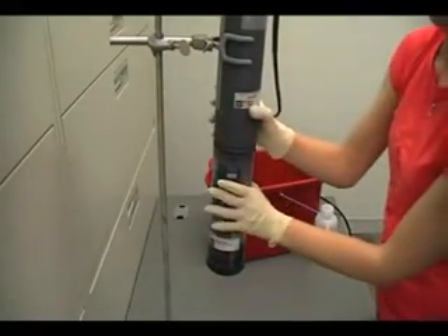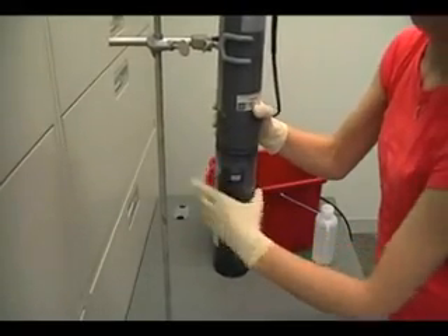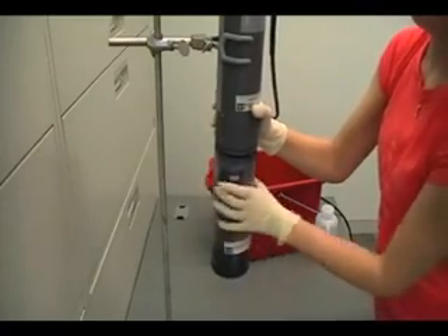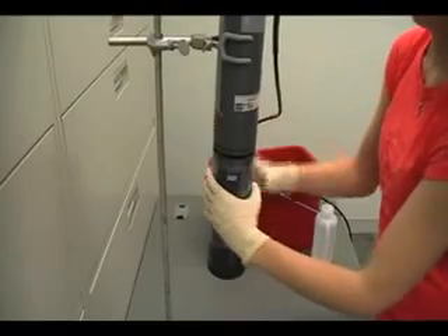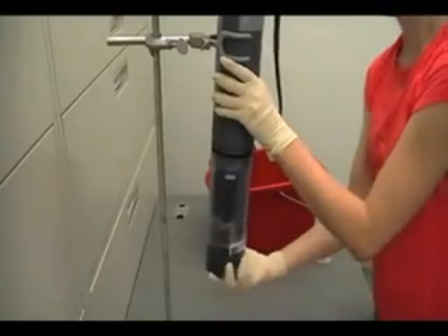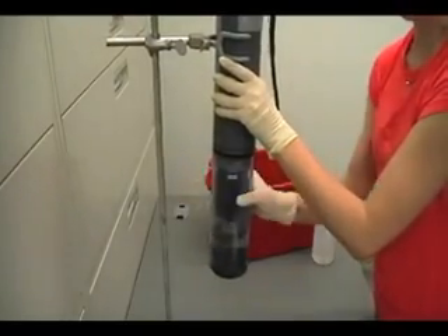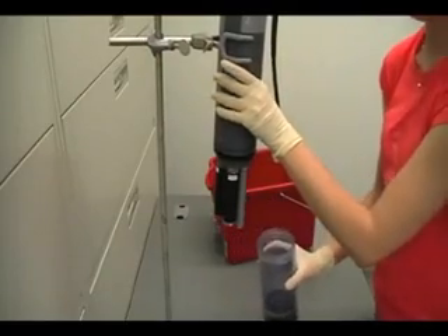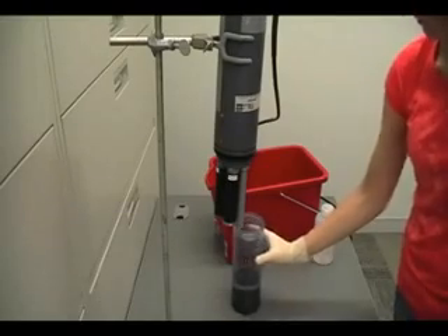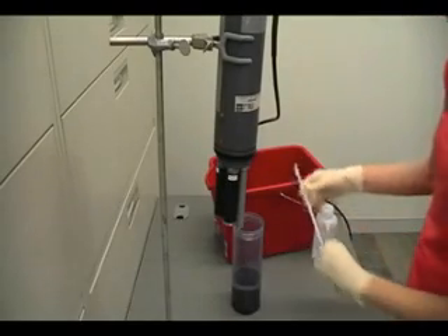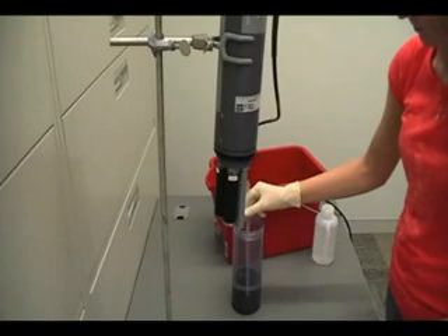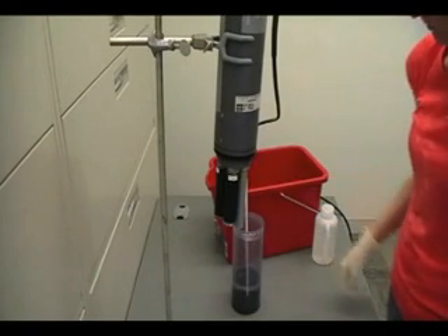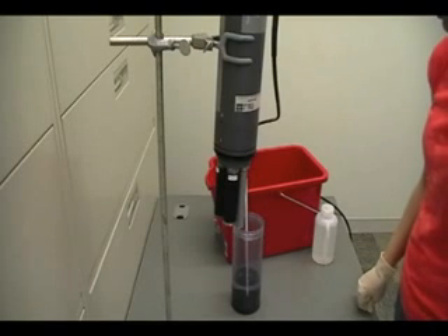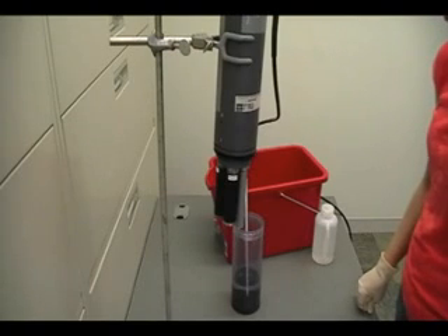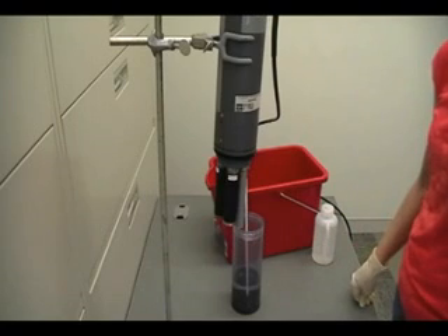Remove the calibration cup and add a thermometer to the solution. Allow sufficient time for the readings to stabilize. Record the value from the thermometer in the box for temperature standard on the calibration worksheet.